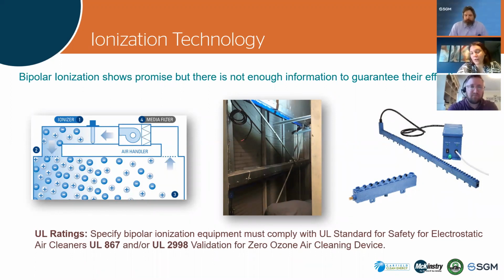And I think maybe it's a good time to also share a little bit of the challenge in getting a standard for this type of technology, and hopefully this day and age is pushing for that in the industry. As far as the UL 867 versus UL 2998, in some of the research we've conducted, there are not many manufacturers that have passed the UL 2998 validation for zero ozone with these air cleaning devices, which is having less than 5 parts per billion detectable ozone. Whereas the UL 867 is 50 parts per billion, which is also still very, very low, but a 50 parts per billion threshold opens up the market a little bit.